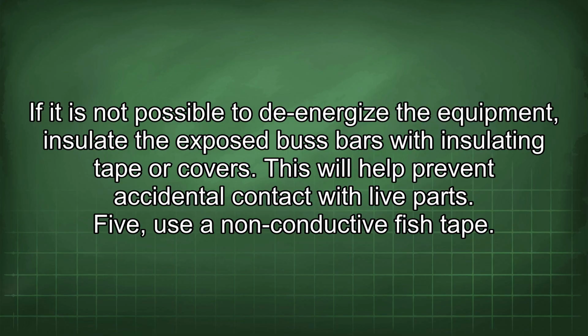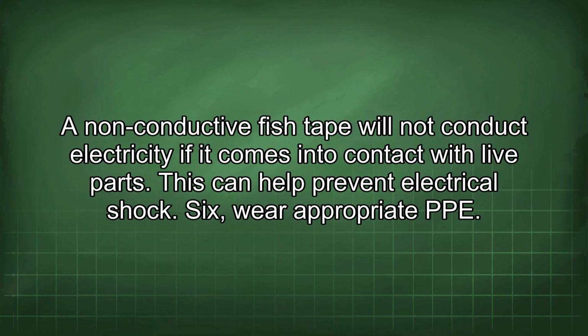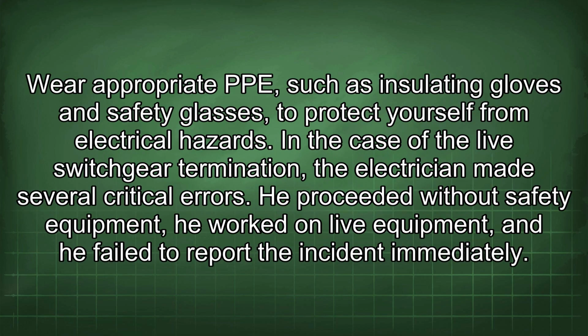5. Use a non-conductive fish tape. A non-conductive fish tape will not conduct electricity if it comes into contact with live parts. This can help prevent electrical shock. 6. Wear appropriate PPE, such as insulating gloves and safety glasses, to protect yourself from electrical hazards. In the case of the live switchgear termination, the electrician made several critical errors. He proceeded without safety equipment, he worked on live equipment, and he failed to report the incident immediately.